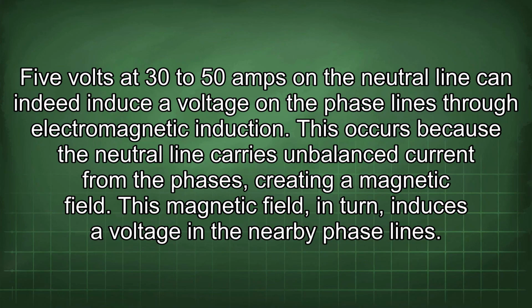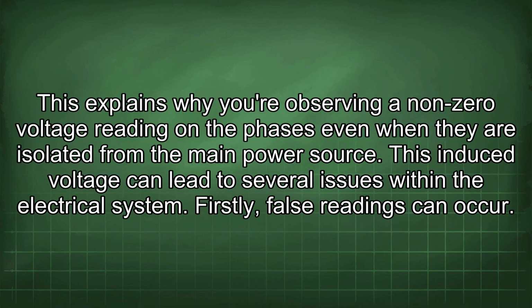5 volts at 30 to 50 amps on the neutral line can indeed induce a voltage on the phase lines through electromagnetic induction. This occurs because the neutral line carries unbalanced current from the phases, creating a magnetic field. This magnetic field, in turn, induces a voltage in the nearby phase lines. This explains why you're observing a non-zero voltage reading on the phases even when they are isolated from the main power source. This induced voltage can lead to several issues within the electrical system.